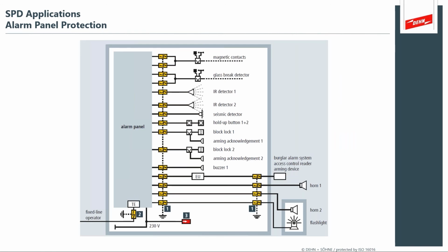alarm panel type protection, where you've got many types of delicate electrical circuits that for an alarm panel are going to be very important for security of your facility. And you've got things like exposed contacts that are either outdoors or near the external of the building. And what's important is that you're providing surge protection devices to prevent the alarm panel from being destroyed, which would, of course, defeat the entire security system. So in an illustration like this, you can see that you've got a full array of backdoor type circuits that can bring electrical damage into that alarm panel.